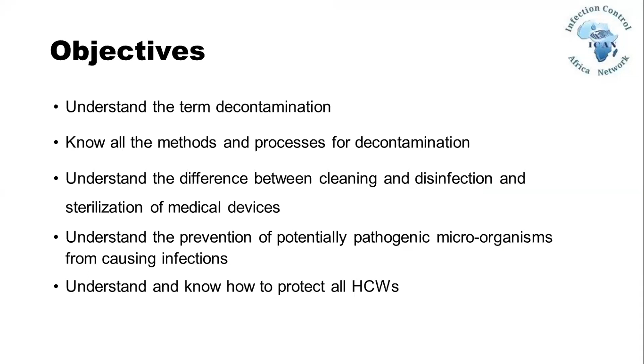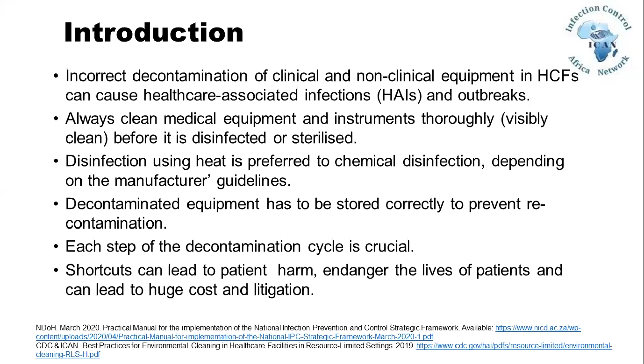The incorrect decontamination of any clinical or non-clinical equipment is vitally important because we can actually drive healthcare-associated infections in our healthcare facilities. Medical equipment and instruments should be thoroughly cleaned before being disinfected or sterilized, and I'm going to explain that a bit in detail. Disinfection using heat is preferred to chemical disinfection, depending on the manufacturer's guidelines. And decontaminated equipment needs to be stored correctly post-cleaning and sterilizing to prevent recontamination. Each step of the decontamination cycle is crucial. Shortcuts can lead to patient harm, endanger the lives of patients, and can lead to huge cost and litigation.